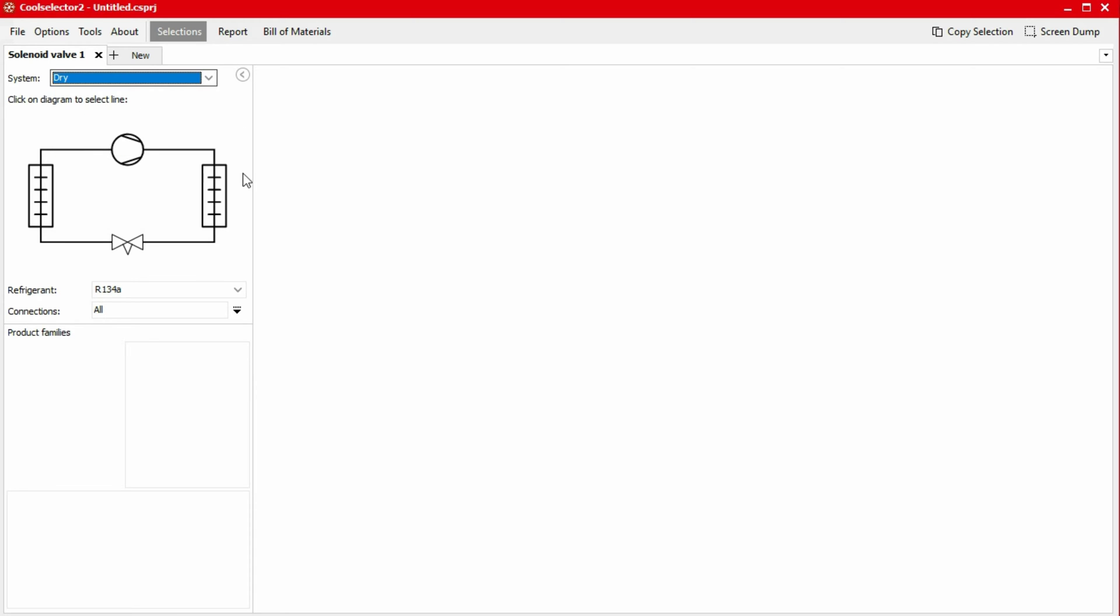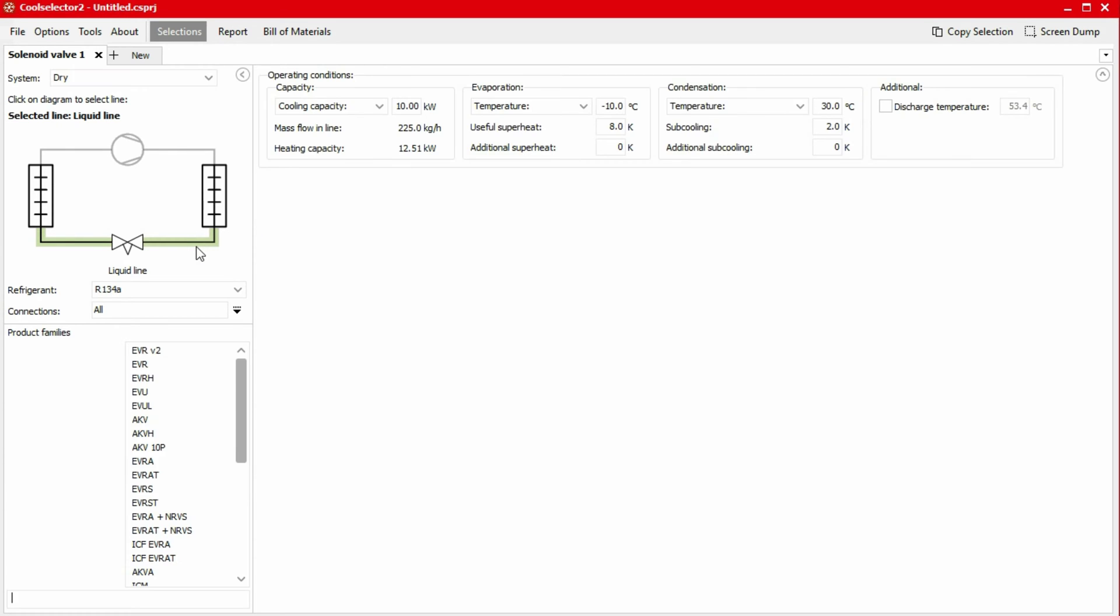We can then select where in the system the valve will be installed using the system schematic. In this case, we require a solenoid valve in the liquid line to be installed before the expansion valve for safety reasons.